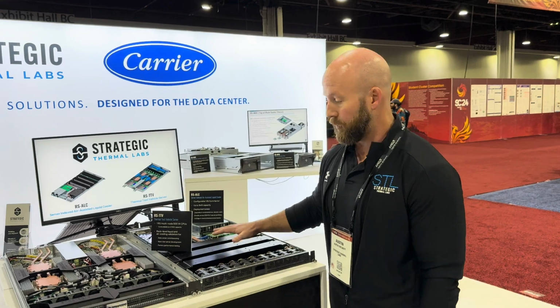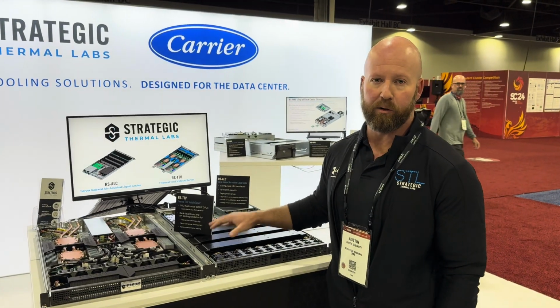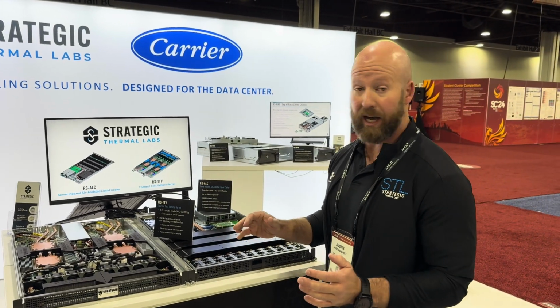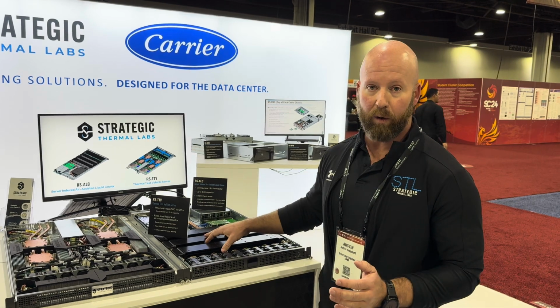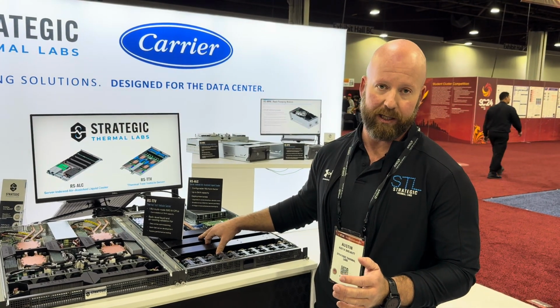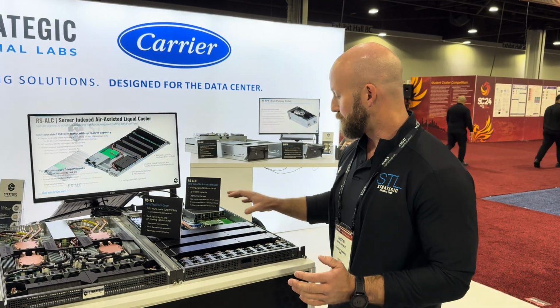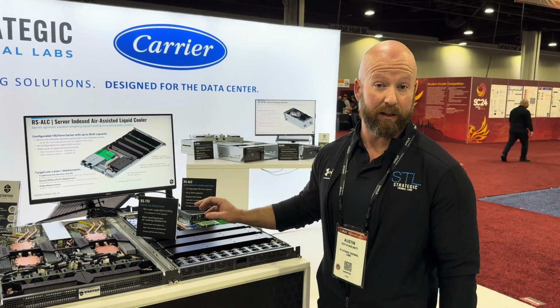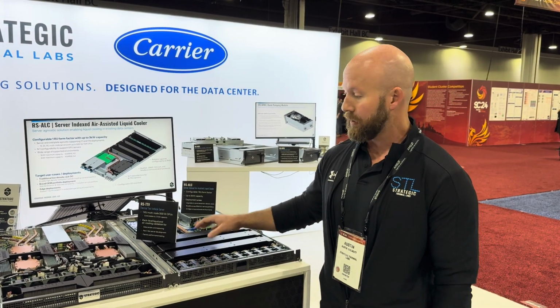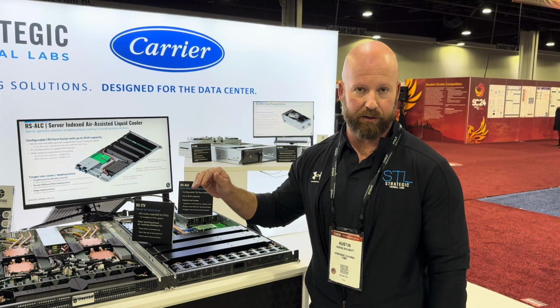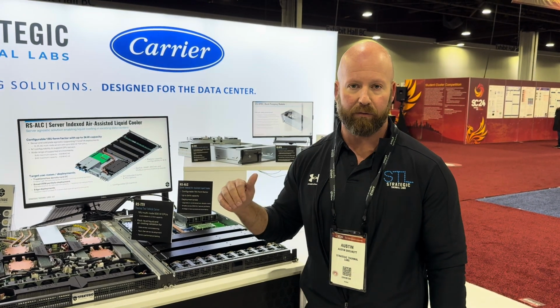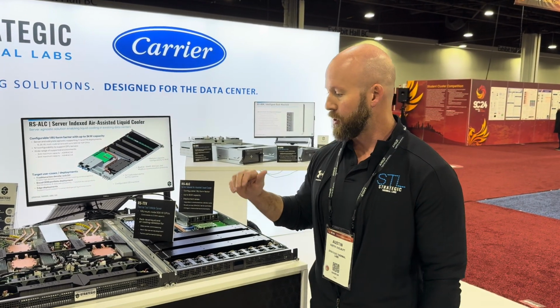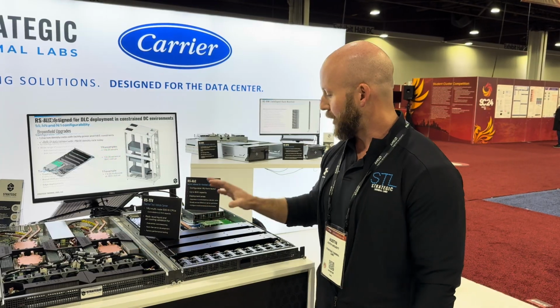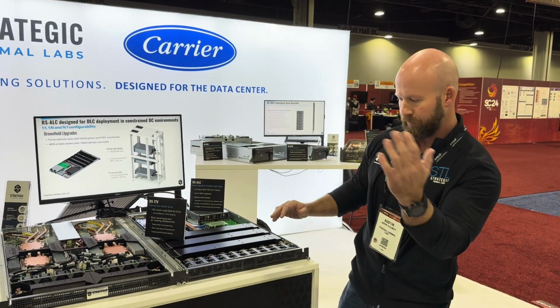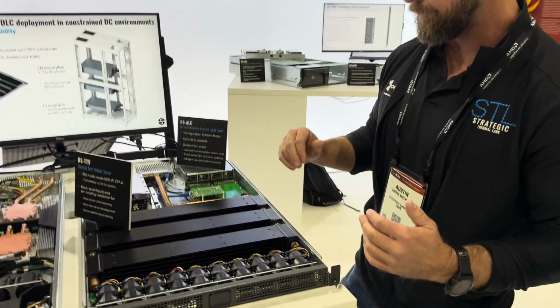Right next to it, we have a device more designed for small co-location enterprise customers. It's a 1U rack mount ALC device, or air-assisted liquid cooling device. This building block has got 3 kilowatts worth of cooling capacity. It mounts in a rack right next to the servers, but it requires no backup rack manifold or pumping module. So you can take a liquid-cooled server and plug it directly into this box. And if you come in here, I'll show you a little closer.